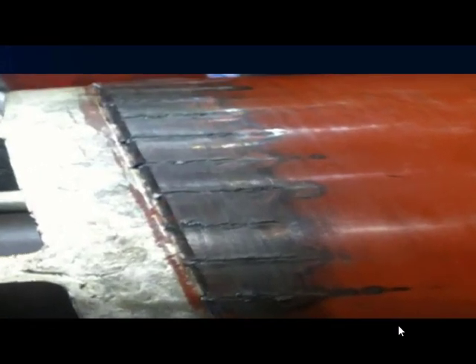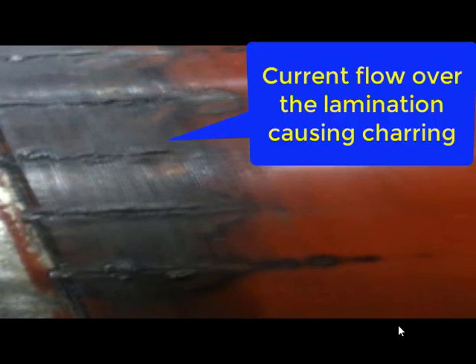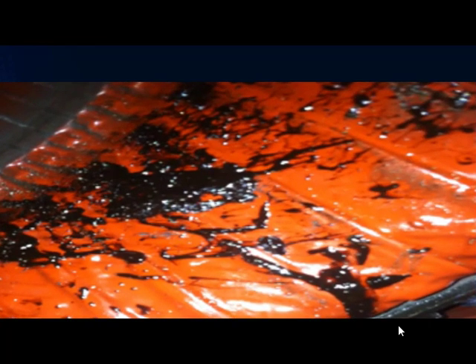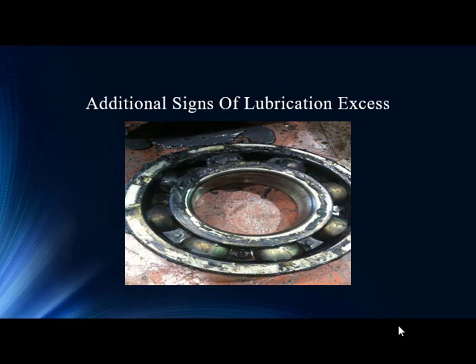When they pull the motor, there's quite an impressive look at the rotor — a lot of heat, and the slots on the rotor show bars starting to separate because of the temperature from current flowing through the tips of the laminations. The aluminum shorting ring at the end looks close to separating from the rotor completely, and the individual laminations — which are designed to be insulated from each other — are visibly charred from stray current flow. Additionally, this is clearly excess lubrication; the roller element bearing is full of grease. As they say, overgreasing kills more than undergreasing.